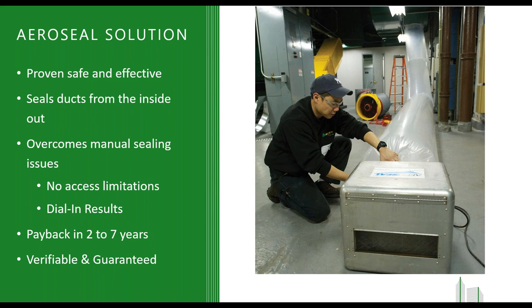So AeroSeal seals up ducts from the inside out. We pressurize the ductwork and send in an aerosol seal that seals up all the holes and gaps that you normally wouldn't be able to see or get to through manual sealing. We monitor that the entire time we're sealing, so we'll tell you how much leakage is there when we start and how much leakage is there after we're done. So you can show your customer and your client exactly what we've done, and you can reset all of the building set points to work as designed.